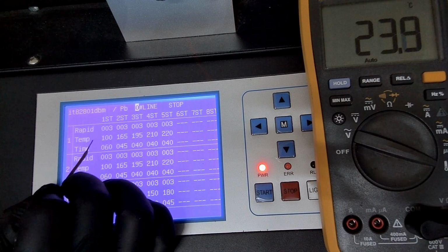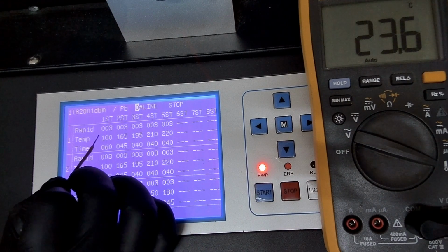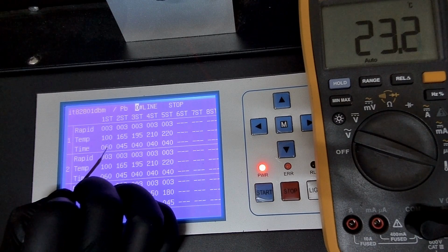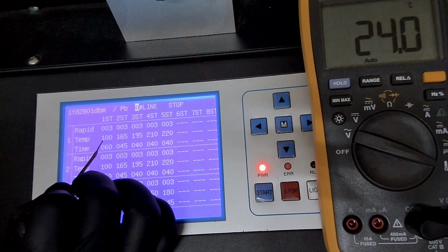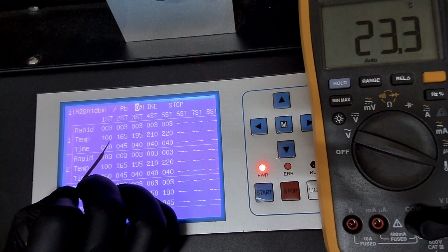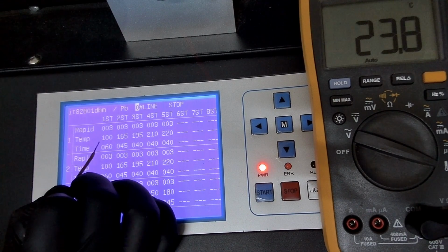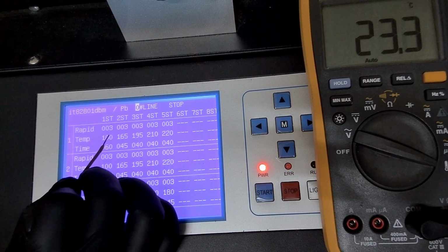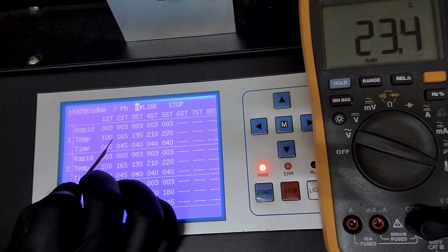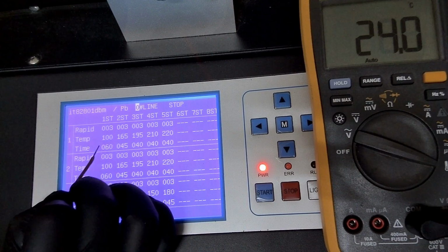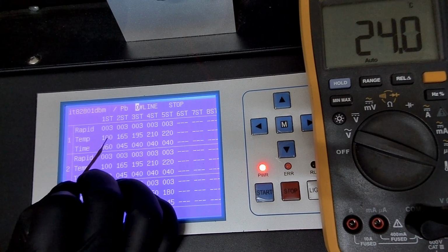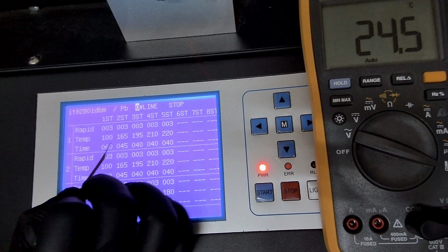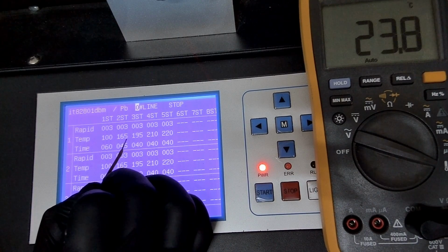Same thing with time at the bottom: it's for how long the machine will hold this temperature before moving to the next stage. For example, the first stage will shoot to achieve 100 degrees within 3 seconds, then hold at 100 degrees for about 60 seconds before moving to the next stage.